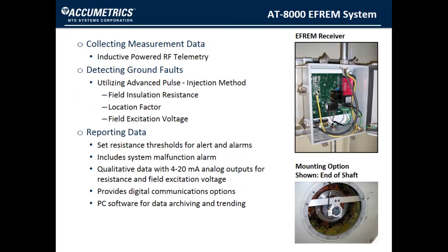Two different alarm outputs allow users to set custom resistance thresholds. Also included is a malfunction alarm. There are two 4 to 20 milliamp analog outputs for reporting fault resistance and field excitation voltage, and included software allows for historical archiving of data so that trends can be examined.